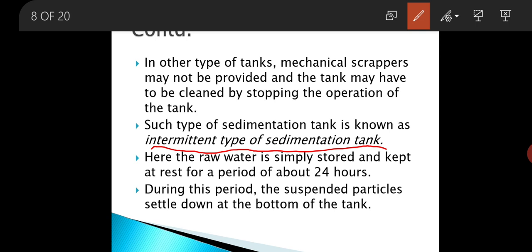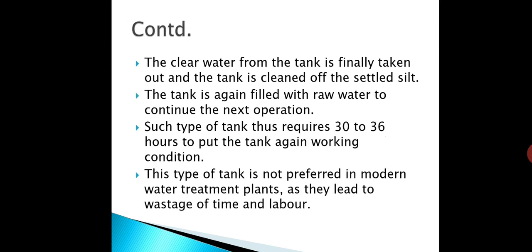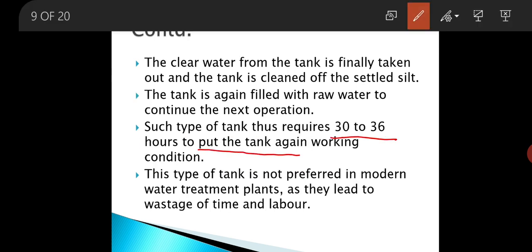After this, the tank is cleaned off the settled silt. After this cleaning operation, this type of tank will require 30 to 36 hours again to come back to working condition. This leads to wastage of time as well as labor. Therefore, continuous flow type of tanks are invariably used these days.